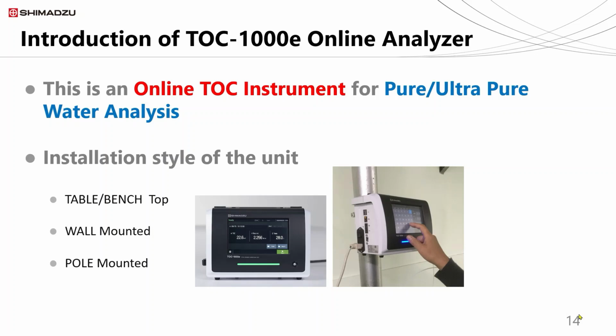As I mentioned before, this is an online TOC analyzer for pure, ultra-pure water analysis. Depending on the online sample line place, the installation site can be one of these. Place on the table, mount on the wall, or directly fix the unit on a pipe. This pipe could be the original online water sample pipe.